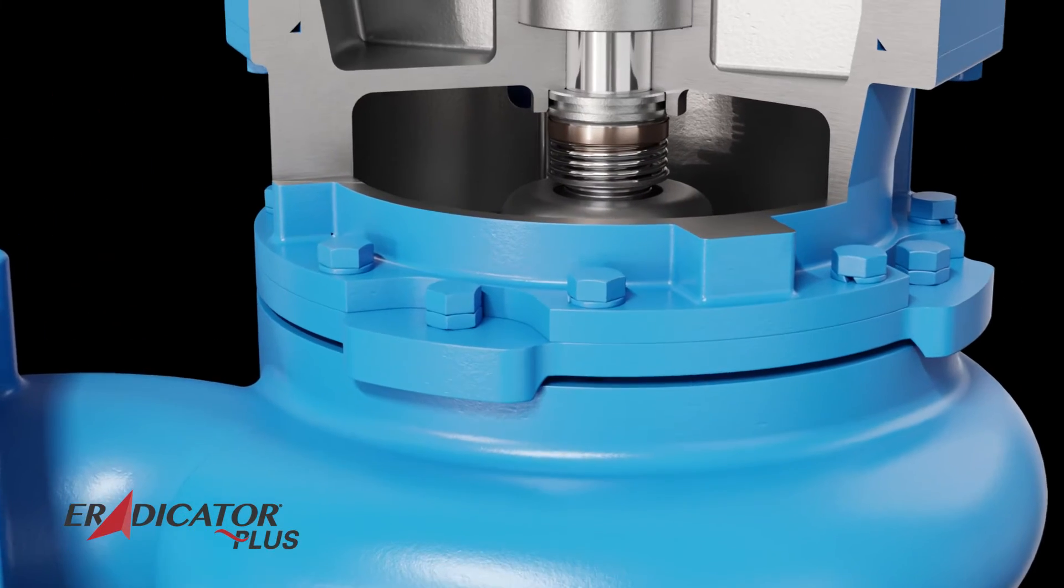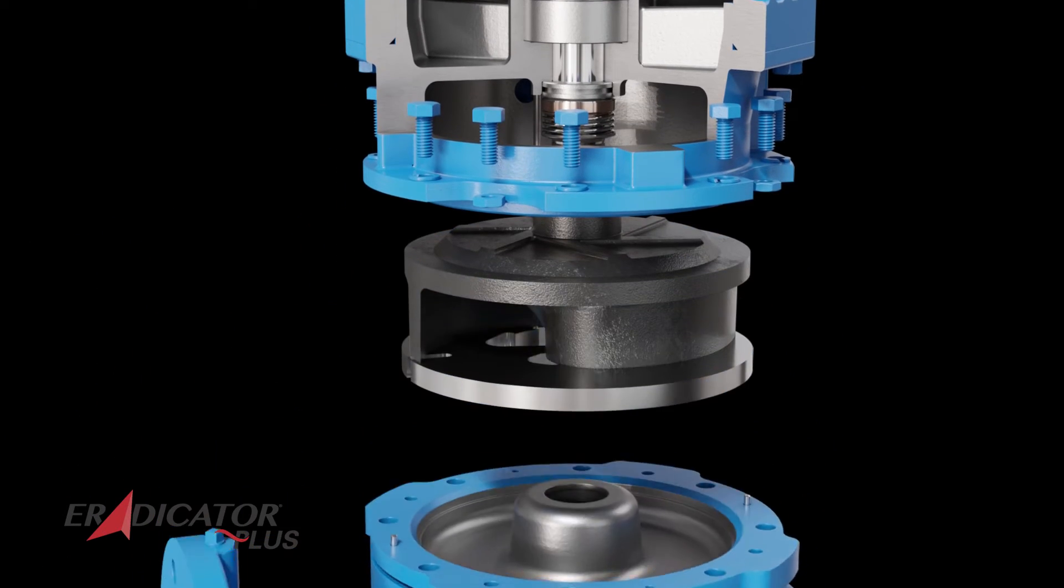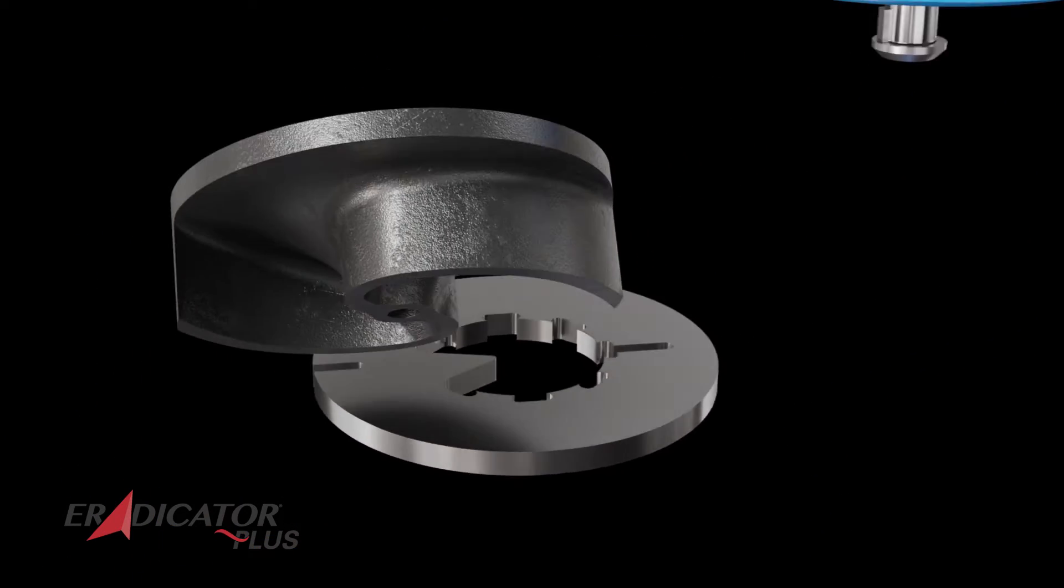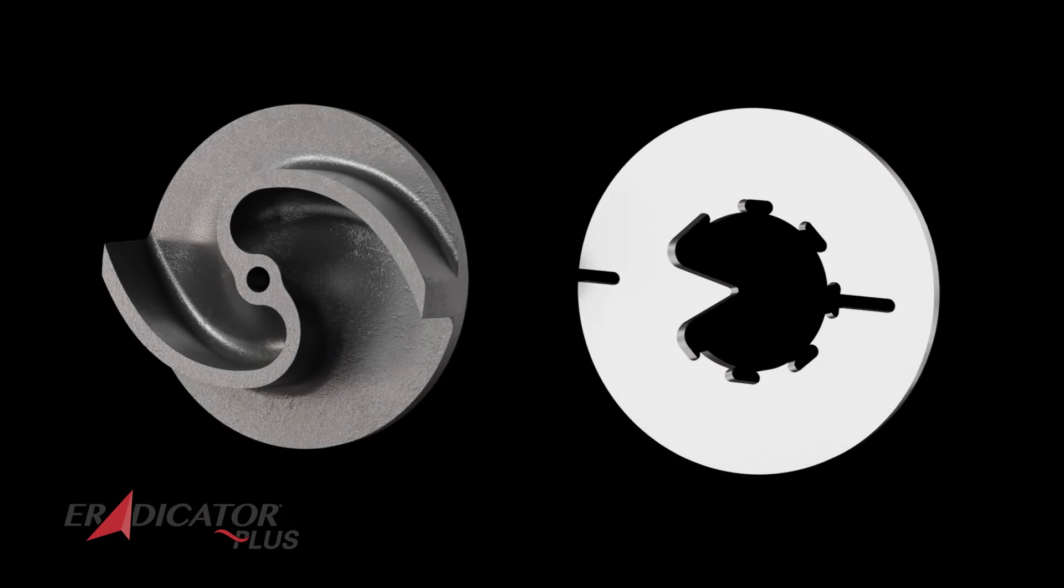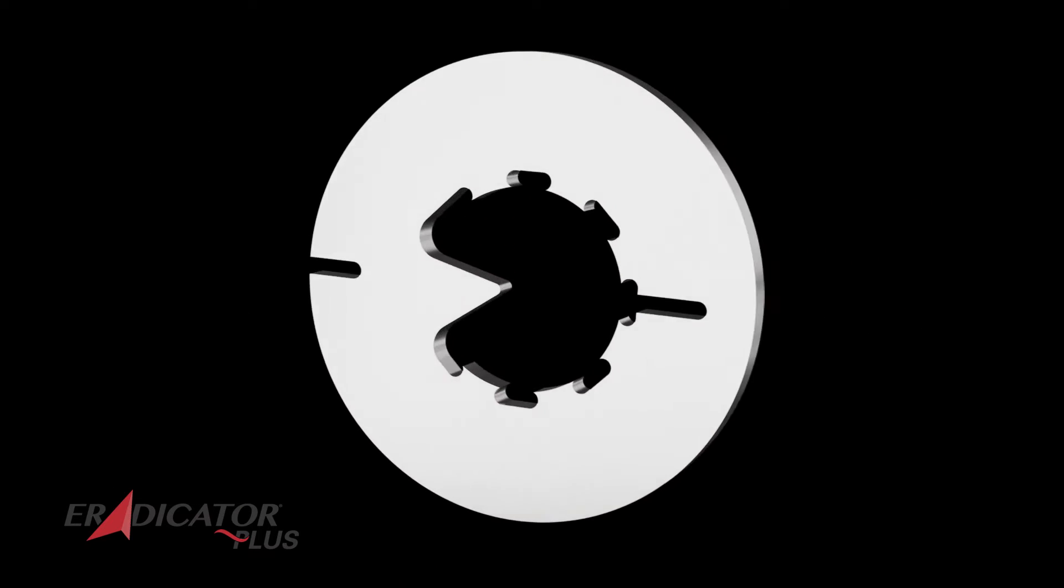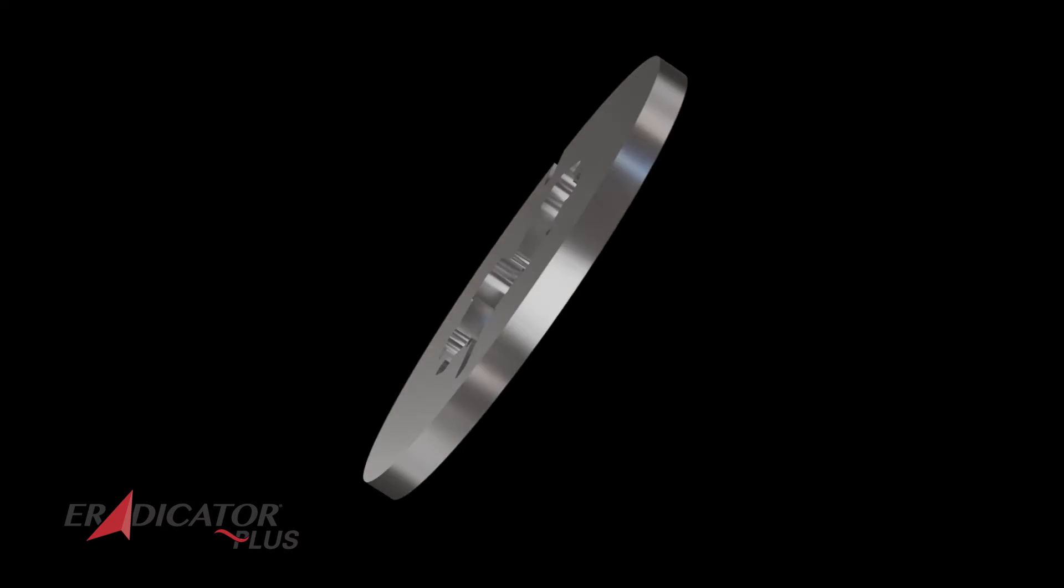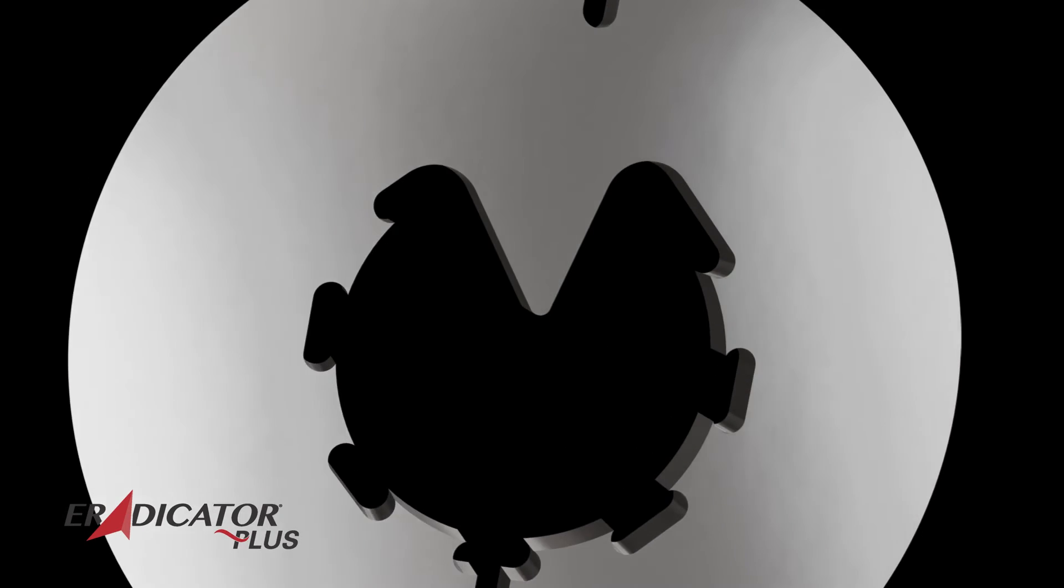Eradicator Plus models offer superior solids reduction technology and are designed for the most aggressive applications, featuring a hardened, continuous vane impeller and the same pump-out vanes as the semi-open impeller. These pumps also come standard with an extra-thick wear plate, utilizing an oversized lacerating tooth when cutting and shredding of organic solids entering the pump is required.